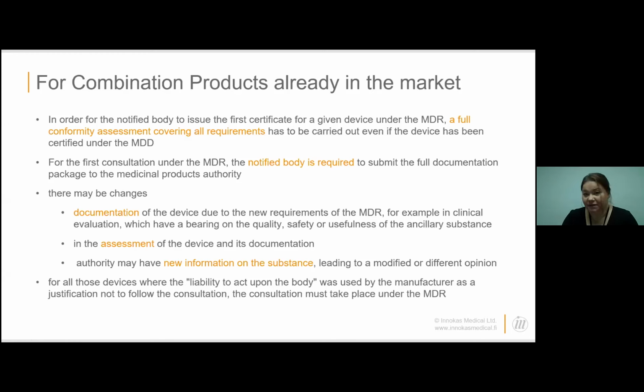The notified body is not the only one deciding on this, so they will need to submit your full documentation package to EMA or to your national authority, whoever is handling this. So be aware that for the first assessment, you will need to cover all your bases. There may be changes that the MDR brought onto the documentation that your device will need. So even though you would have a legacy device, which by definition in the guidances will have a somewhat leaner pathway, the documentation they're requesting still needs to be there. The evidence can be referred to as the one that you created while your product was on the market, but the documentation still needs to follow the technical file description that is in the MDR.